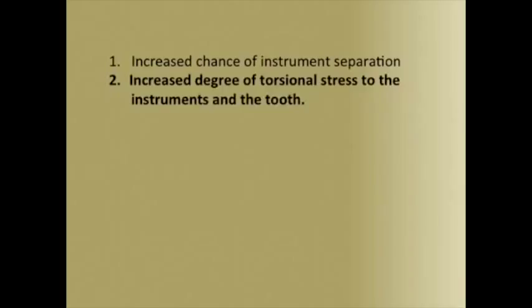An example of torsional stress would be the bind that results from engaging and then locking into tooth structure at unpredictable points of constriction along the lengths of the root. Another cause of breakage is cyclic fatigue. As the name implies, it is a result of repeated stresses to the instrument — none of which alone would cause the instrument to break, but cumulatively lead to failure. An instrument negotiating a curved canal in rotation will undergo a bending motion every 180 degrees, producing repetitive cycles of compression and tension. Binding is not required for breakage, although the combination of cyclic fatigue and torsional stress together makes the instrument more vulnerable to separation.